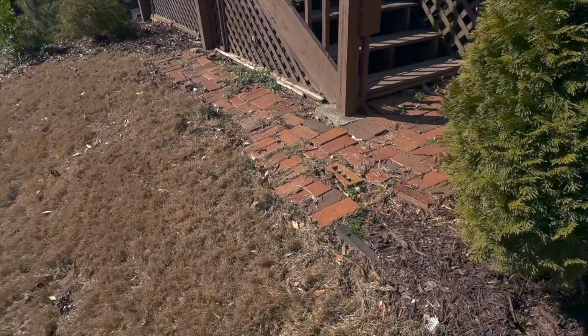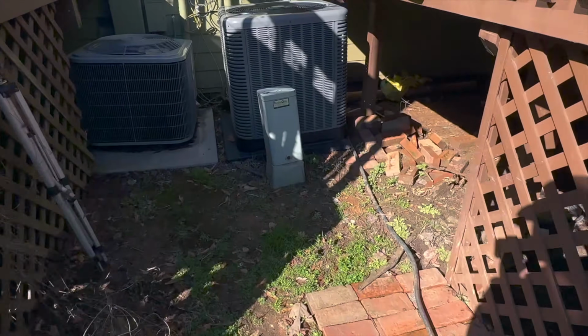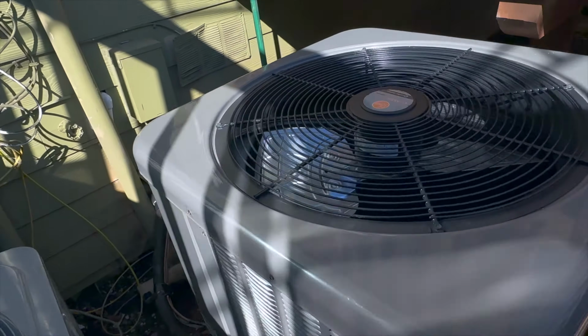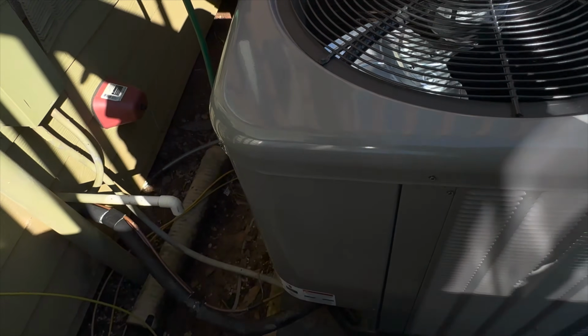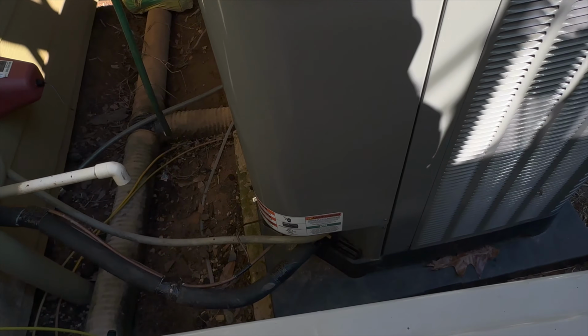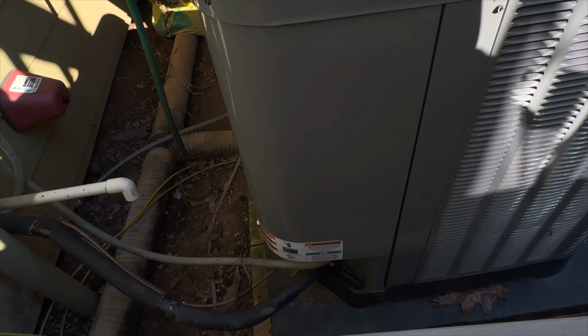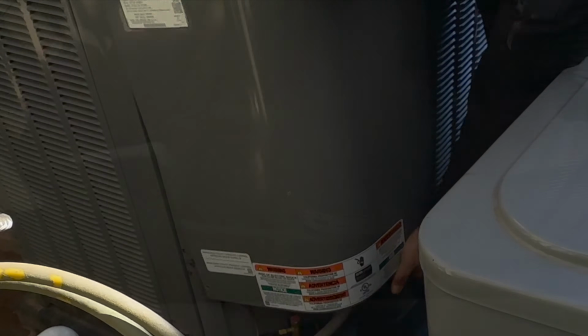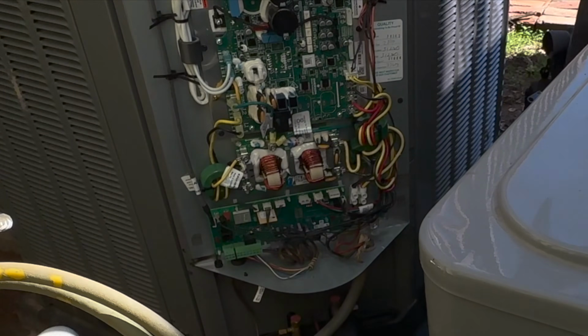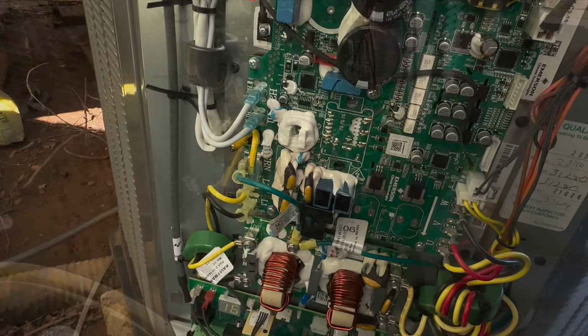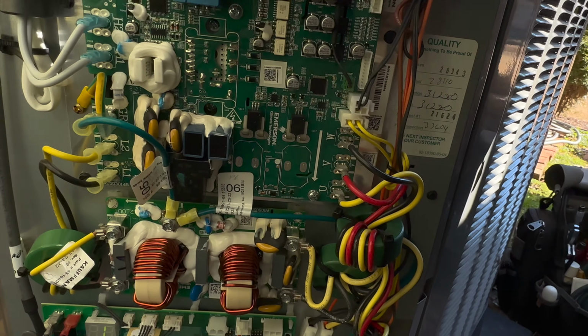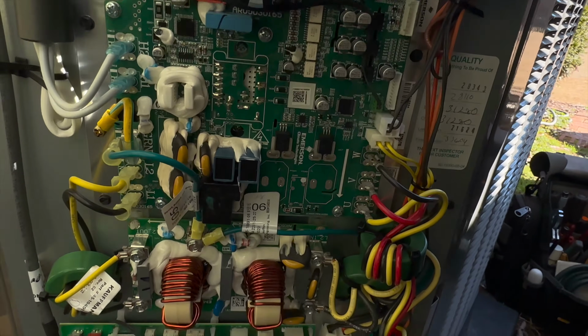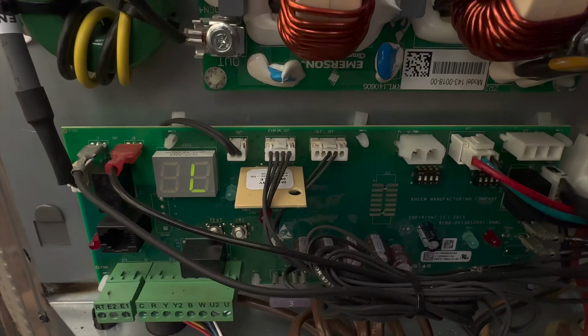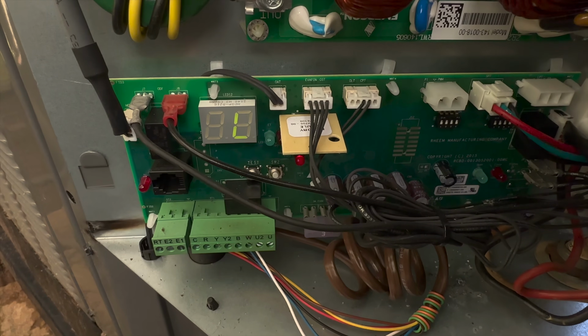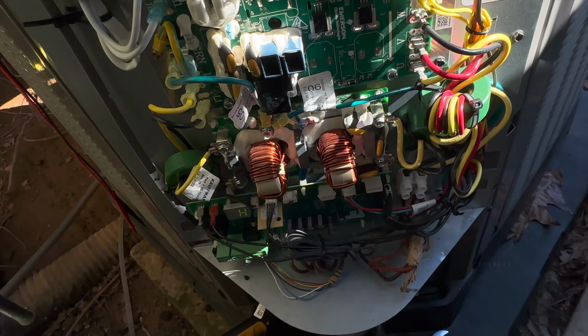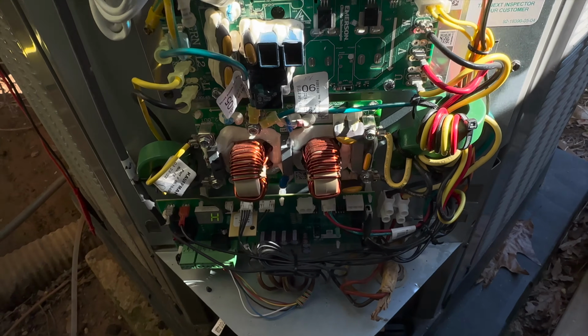All right, let's see what this unit's doing. This thing should have some type of code on it right now because it is not turning on, and the indoor air handler is. All right, fancy. So we are getting a code down here, L16. That L16 is some type of inverter fault.